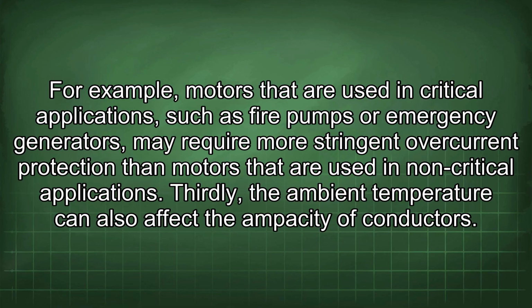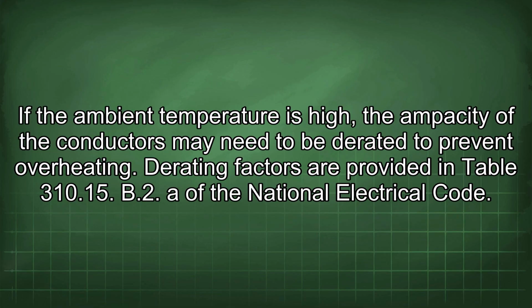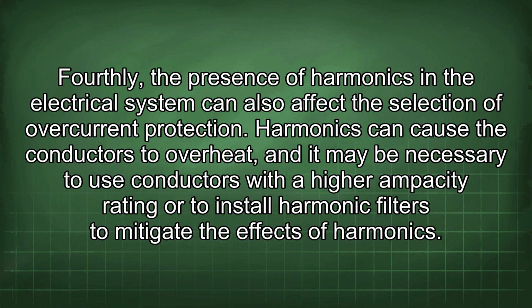Thirdly, the ambient temperature can also affect the ampacity of conductors. If the ambient temperature is high, the ampacity of the conductors may need to be derated to prevent overheating. Derating factors are provided in Table 310.15(B)(2) of the National Electrical Code. Fourthly, the presence of harmonics in the electrical system can also affect the selection of overcurrent protection. Harmonics can cause the conductors to overheat, and it may be necessary to use conductors with a higher ampacity rating or to install harmonic filters to mitigate the effects of harmonics.